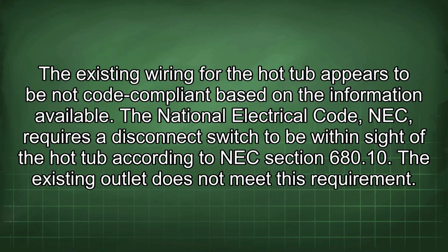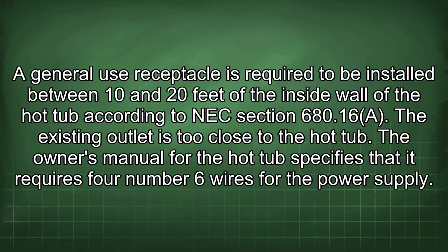The existing wiring for the hot tub appears to be not code compliant based on the information available. The National Electrical Code, NEC, requires a disconnect switch to be within sight of the hot tub according to NEC section 680.10. The existing outlet does not meet this requirement. A general use receptacle is required to be installed between 10 and 20 feet of the inside wall of the hot tub according to NEC section 680.16a. The existing outlet is too close to the hot tub.